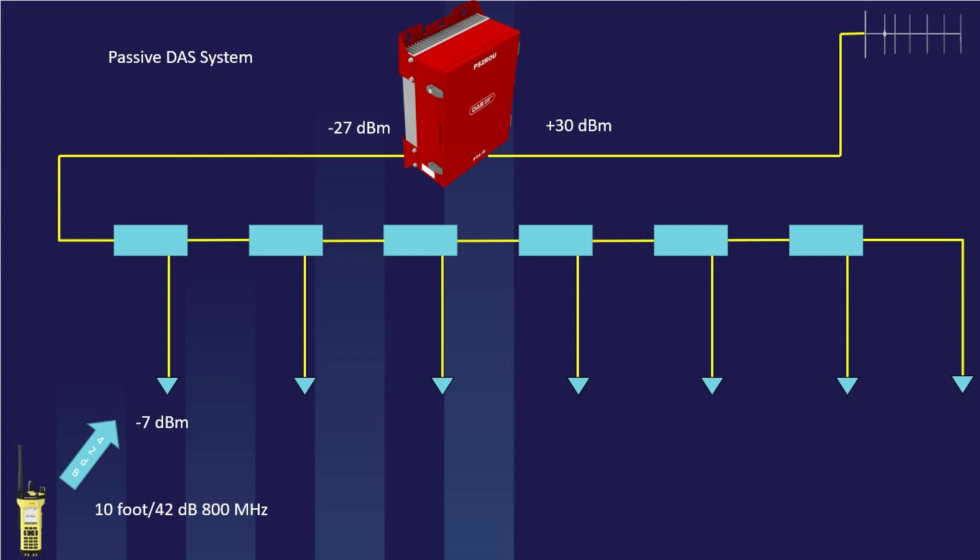This BDA in this situation should be set for 57 dB of gain. No more, no less. No channel chasing, no power chasing, none of the other things that cause noise problems. Just simply 57 dB of gain. As the portable moves away from one antenna and closer to another, the signal will change. Service antenna spacing will be determined by the link budget for the donor uplink, not by the downlink. If you do it by downlink, you're going to end up with too few antennas in your installation.